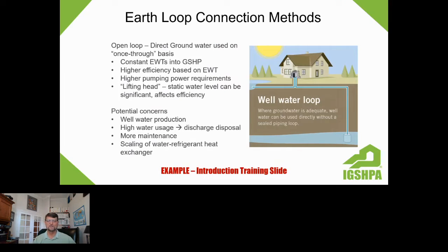There are multiple ways to connect a geothermal system to the earth, whether it's a water well system, such as this slide depicts, or a closed loop system where you would use the high density polyethylene plastic pipe that's installed in either a horizontal trenching system or a vertical loop. There are multiple ways to do that, depending on the property and the conditions available and the local cost. So we cover all those methods in general to give people that overview so that they have a better concept about the whole system.